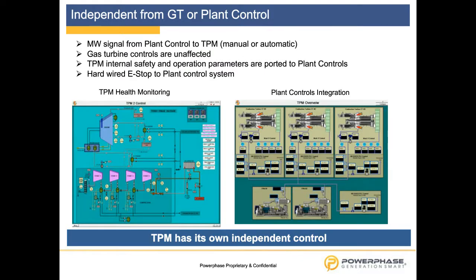Here, what we see is some screenshots from existing operations. We get the megawatt signal from the plant control center, either manually or automatic. I mentioned that. Gas turbine controls are unaffected. We read out permissive signals from your gas turbine controller or from your plant controls.